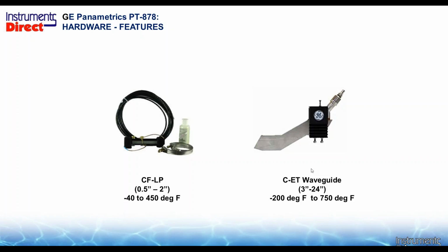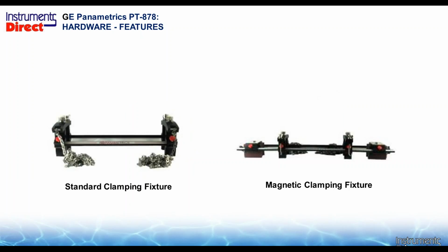And for those with really, really high temperatures, we have the blade or the waveguide. And this is an expensive puppy. You need to have your little strips of gold or silver or something to run the process under it, to interface between the two. So take out your checkbook if you're going to use this as a survey device. This is used a lot in hot oils and diaphragm applications. So it shows you the integrity and expansion that you can use with the technology. So should you have the core device, there are some unique sensors for unique applications.